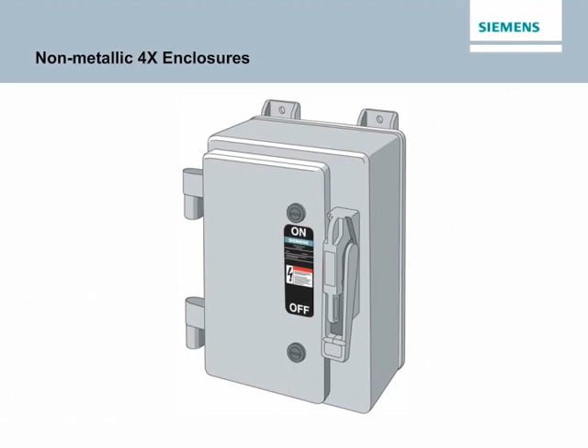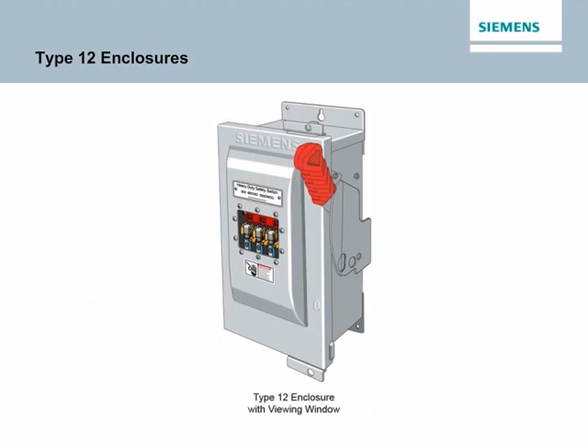Another safety switch enclosure is a fiberglass reinforced polyester version of the 4X enclosure. This non-metallic 4X enclosure has no external metal parts. Type 12 enclosures provide a degree of protection against dust, falling dirt, and dripping water in indoor locations, but are not intended to protect against conditions such as internal condensation.